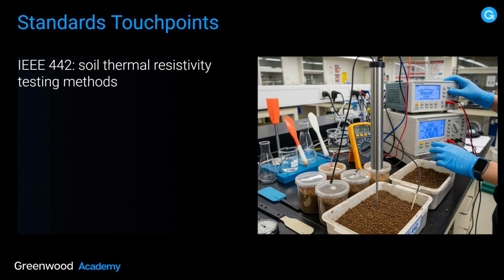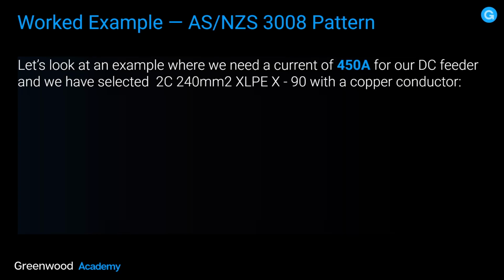3008 is the one that seems to be most misunderstood, especially when it comes to cable derating. And of course, there's AS3000, which is the master standard. Standard touch points, IEEE 442, soil thermal resistivity testing methods. Let's look at an example where we need a current of 450 amps for our DC feeder, and we have selected 2-core 240mm XLPE X90 with a copper conductor.